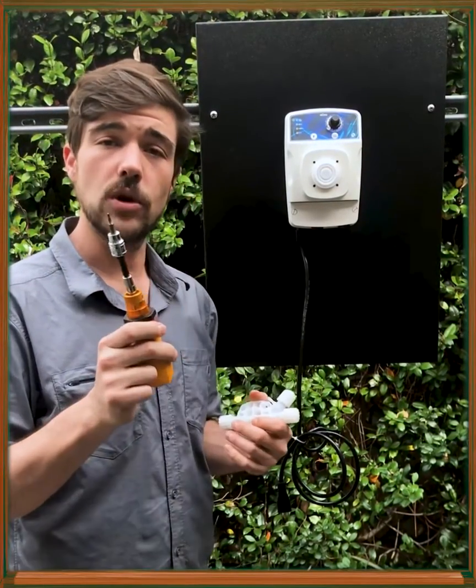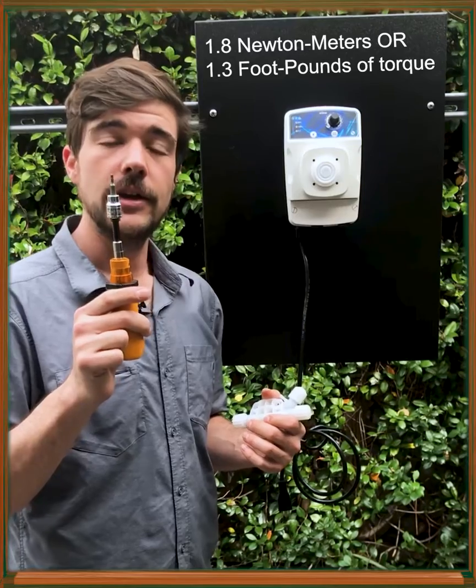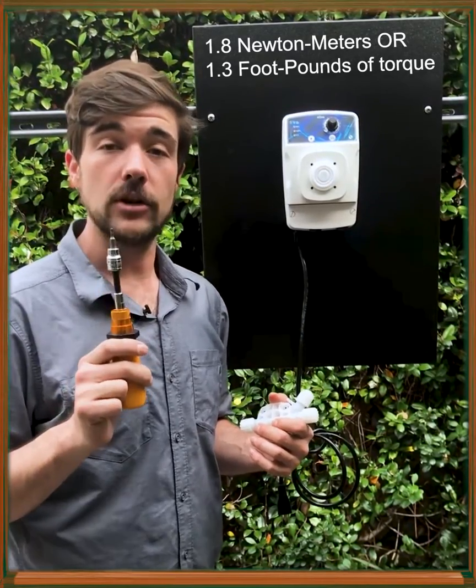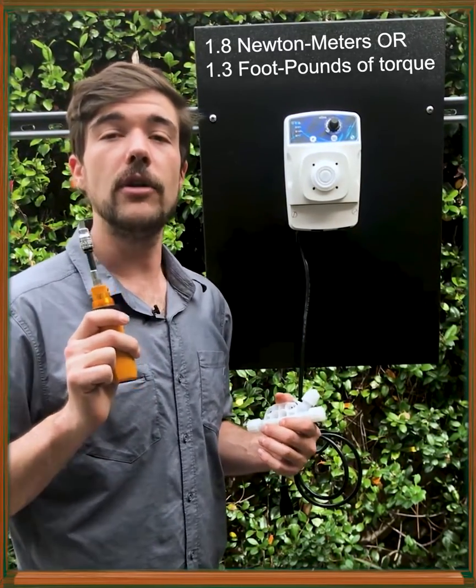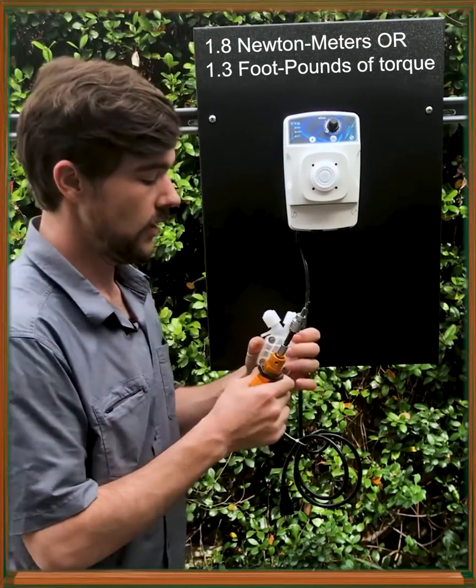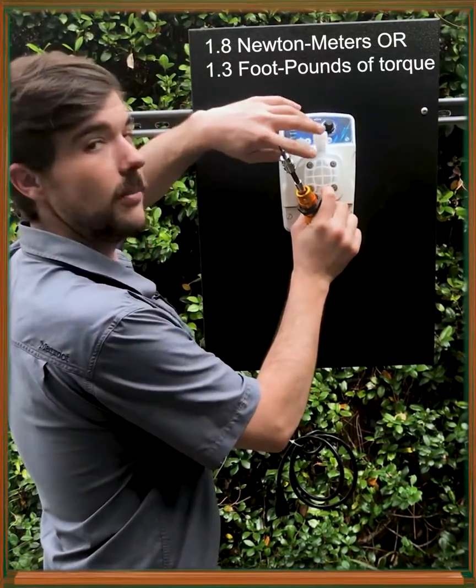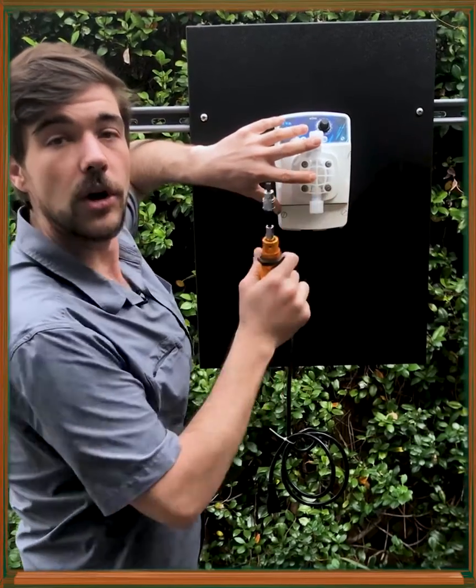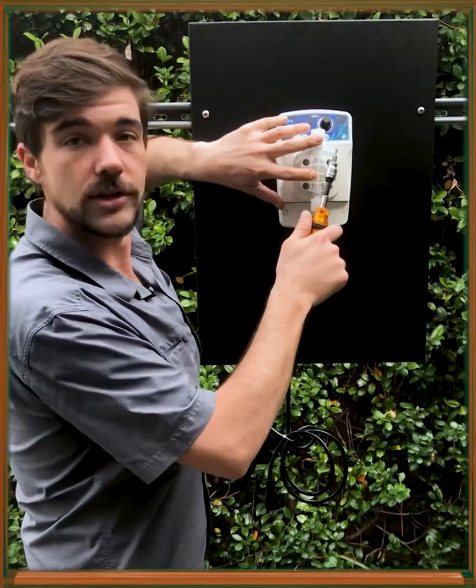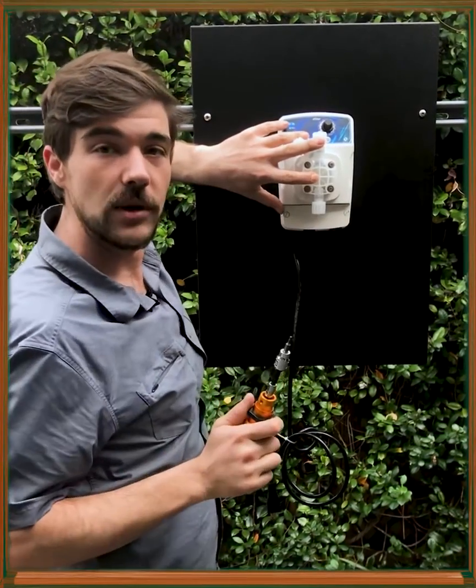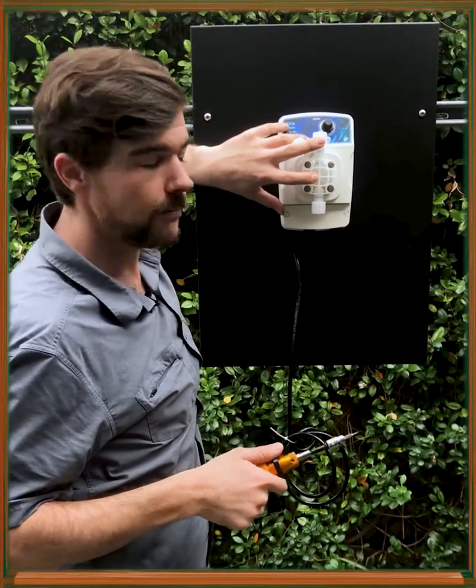If you have a torque wrench, set it to 1.8 Newton meters or 1.3 foot-pounds of torque force. Once you have the pump head aligned, tighten these down in a crisscross pattern, just like tightening a tire onto a car.